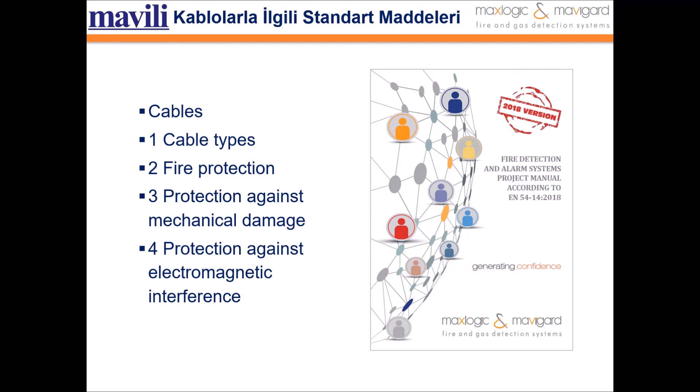Protection against mechanical damages. Cables must be adequately shielded. Cables can be attached to cable tray channels, etc. If installed, they must be separated from other cables. They should not be installed in the same tray with low voltage cables. If there is only one tray for extra low voltage and low voltage cables, they must be separated from the low voltage cables by a metal physical barrier.